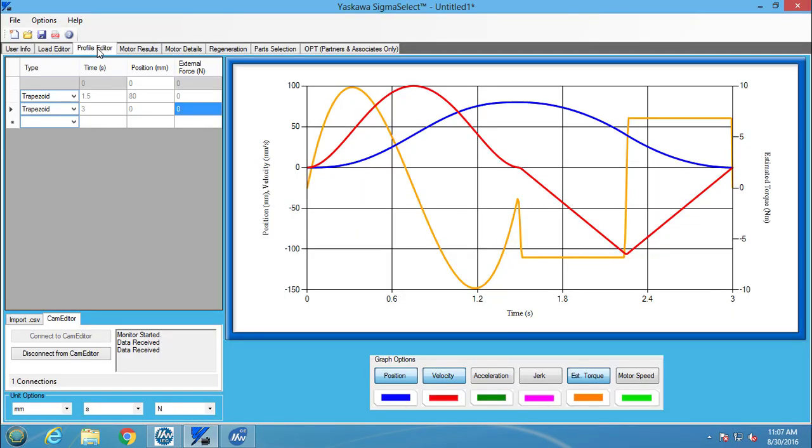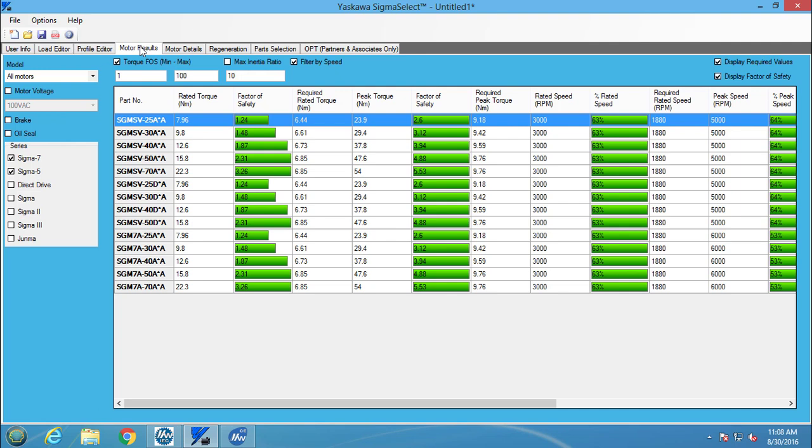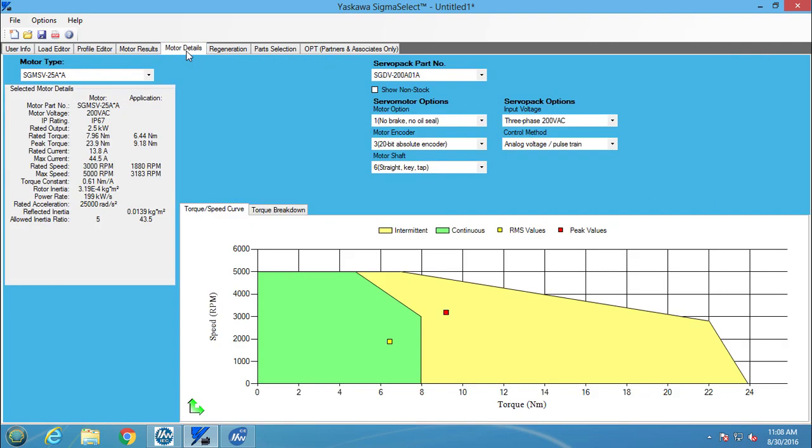Since the curve type has been changed, the motor results screen updates as well. The motor details tab then shows the updated torque and speed curve graph. Notice that the polynomial curve type resulted in higher peak values. You can see therefore how changes to the profile in CamEditor are reflected in Sigma Select and an accurate sizing result is obtained.